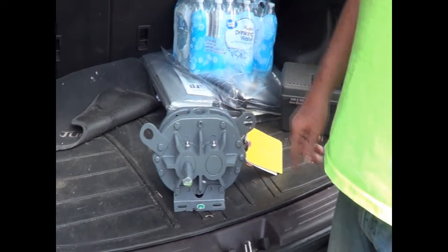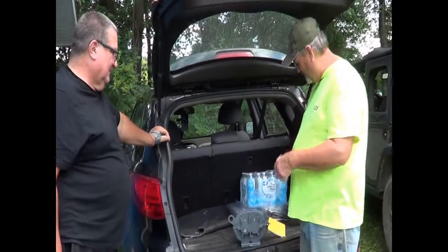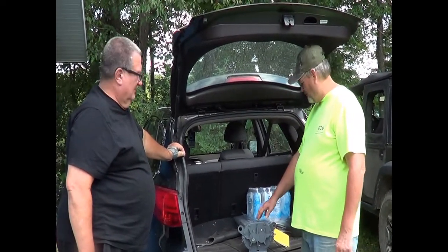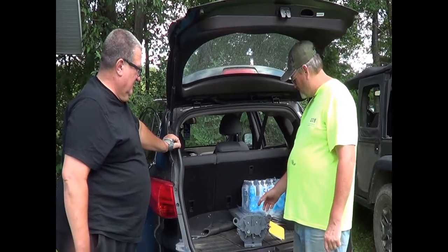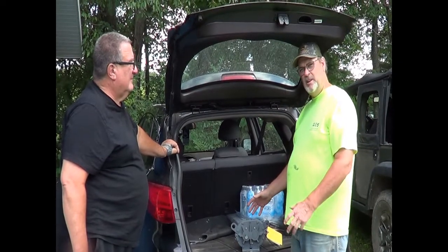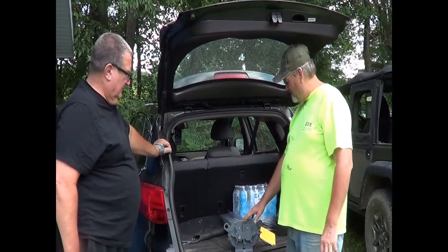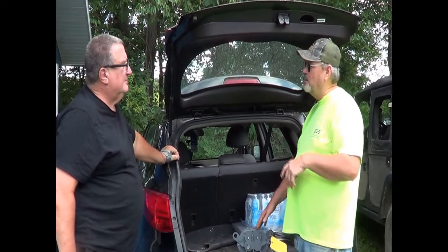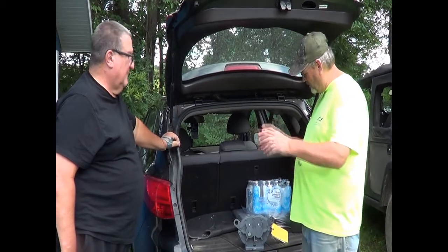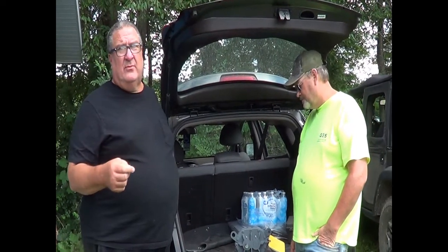Yeah, I don't mind — and that's the problem. That's where I told my boss we've got to do something different, we've got to change the application. Talking to you, I need to make sure not just that the air coming into the air cleaner is kept clean, but I need the whole thing to be kept clean — the whole application. This site has vents all over the place so it can stay cooled down. But we're having a lime leak; there's lime getting all over everything. I can go through more filters with a cover, but it's still not good. So I'm going to change where it's positioned and put it outside.